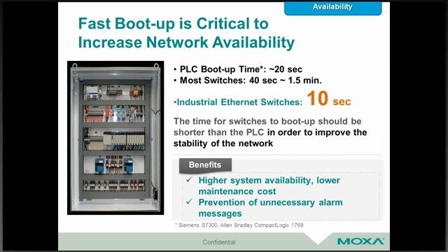Another best practice for availability is to make sure you have a very fast boot up time on the devices running on the network. What we've seen is that a typical boot up time for a PLC is roughly 20 seconds. Most switches, especially those on the commercial or enterprise side, will take anywhere from 40 seconds to about 1.5 minutes to boot up, which is significantly longer than a common industrial PLC. Industrial Ethernet switches, by comparison, typically have a boot up time of around 10 seconds, which is significantly faster. What we typically recommend as best practice is that the time for switches to boot up should be shorter than the PLC, in order to make sure the stability of the network is in place. This is especially important with safety PLCs, which will shut down the entire safety network if the network devices are not already up and running.